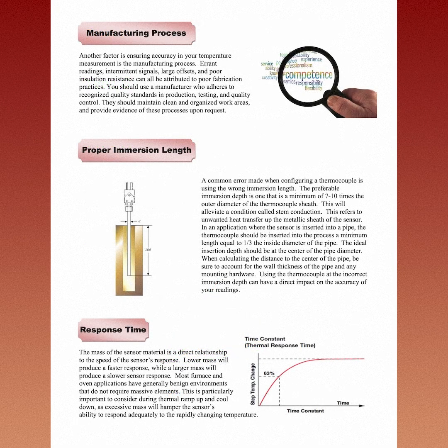Manufacturing process. Another factor in ensuring accuracy in your temperature measurement is the manufacturing process. Errant readings, intermittent signals, large offsets, and poor insulation resistance can all be attributed to poor fabrication practices. You should use a manufacturer who adheres to recognized quality standards in production, testing, and quality control. They should maintain clean and organized work areas and provide evidence of these processes upon request.